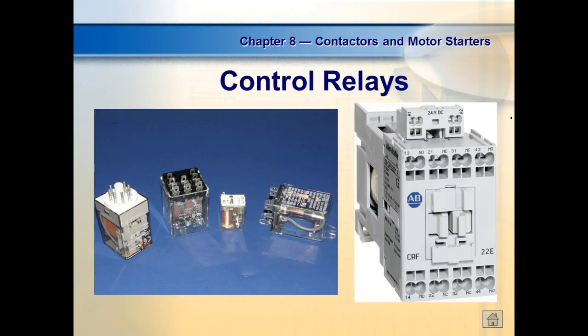The control relay we have is going to be one of these. We call it a peanut relay. But you'll be able to actually look inside of it and see the contact. Normally, the wiring diagram for the contact is on the label on the outside. A lot of these are designed to plug into sockets.